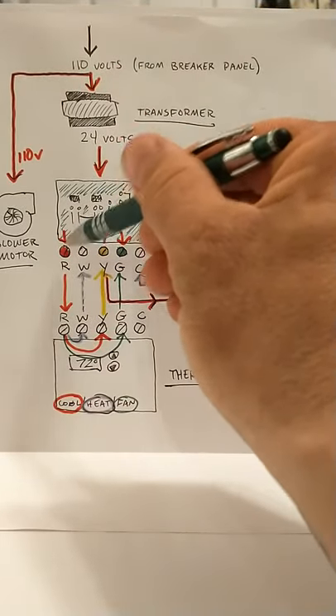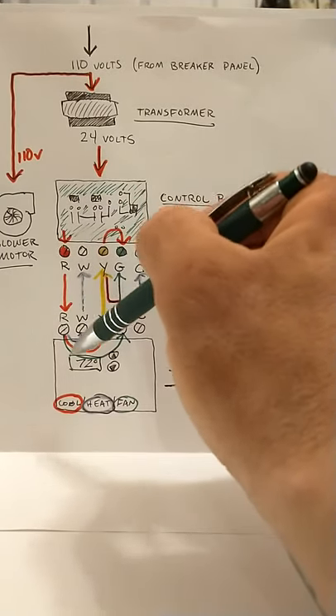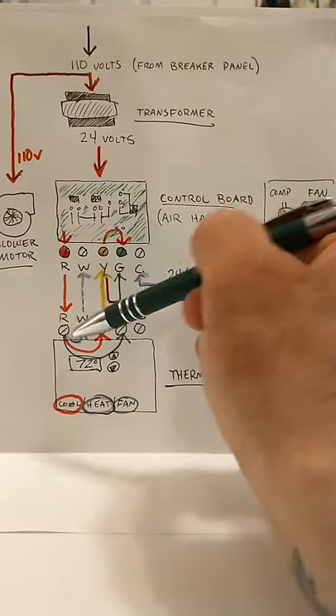Now the flow path here, you always have 24 volts from your R terminal at your air handler running up to the R terminal at your thermostat. So that red wire will always have 24 volts to it up to this point right here.